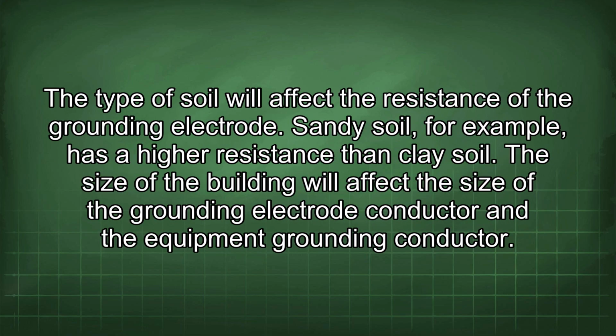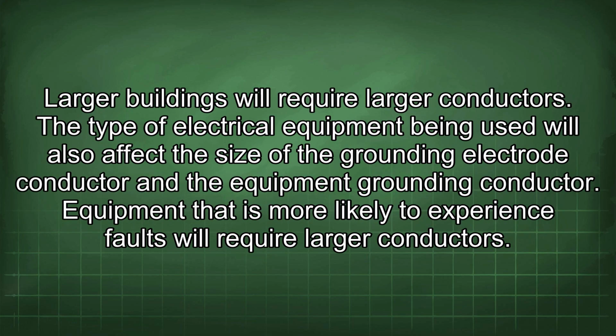The type of soil will affect the resistance of the grounding electrode. Sandy soil, for example, has a higher resistance than clay soil. The size of the building will affect the size of the grounding electrode conductor and the equipment grounding conductor. Larger buildings will require larger conductors. The type of electrical equipment being used will also affect the size of the grounding electrode conductor and the equipment grounding conductor. Equipment that is more likely to experience faults will require larger conductors.